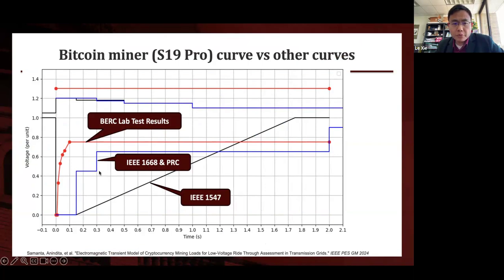If the system operator were to institute such standards for these mining loads, they would all fail, because lab testing shows they can only sustain up to about 9 milliseconds, while the standard requires about 18 times longer. That raises a very interesting question: what should be a proper standard for these large computing loads when it comes to low voltage ride-through?